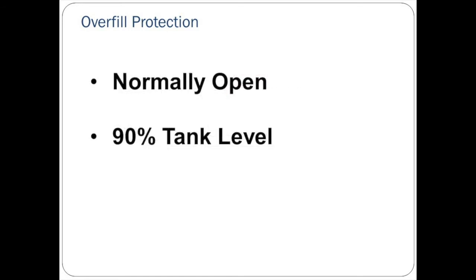The electrical contractor has already installed the overfill alarm wires between the VST control panel and the output module on the fuel management system. The VST control panel supplies 24 VDC to this normally open overfill alarm relay. The overfill alarm relay is to close at 90% tank level. This relay closing will cause the Green Machine to go into alarm and will prevent the Green Machine from running for 2 hours until after the overfill condition ends. When programming the relay, label it GM Overfill Alarm.